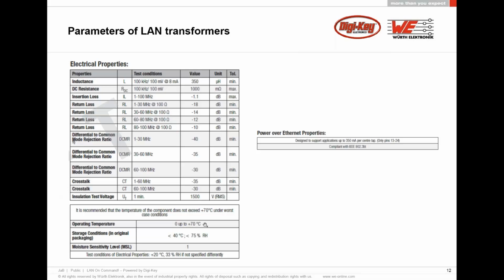If we have an environment of 70 degrees, I should not be using that transformer with PoE, because I already have 70 degrees ambient temperature. So if my transformer is going to become hotter, I can have effects on the inductance, since if the temperature rises, the inductance will go down. So the answer is actually no, we cannot use transformers outside of the operating temperature range.